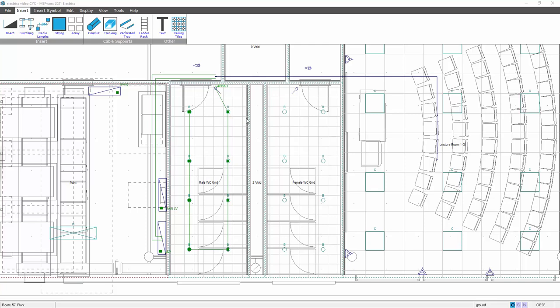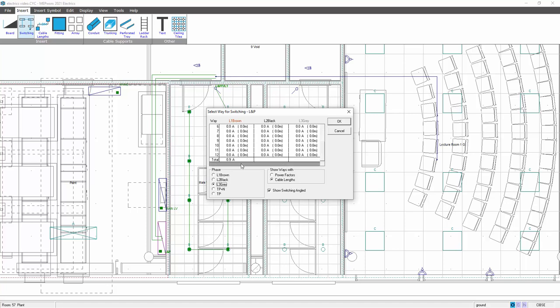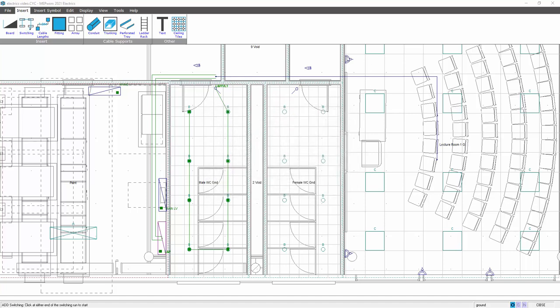If I wanted to do a ring main, it's the same, but I need to allocate these to my board first of all. So again, I need to go down to the lighting and power board, insert switching, select the way and phase that I want to put the ring main on, so I'm going to say L3 grey. And while you're setting your board up, you've got a little slider bar here. At the bottom here, you get the total of your board. So as you're building your board together, you can try and balance it as best as possible. So I'm going to go for L3 grey, OK that.